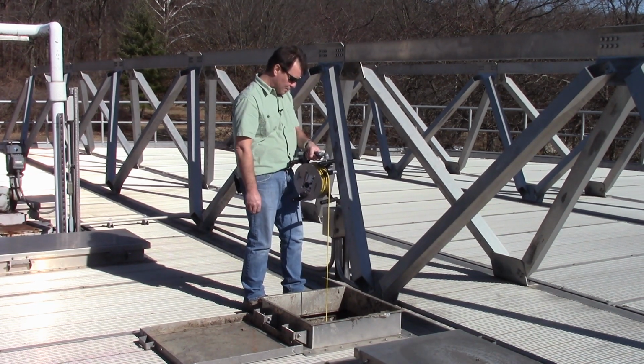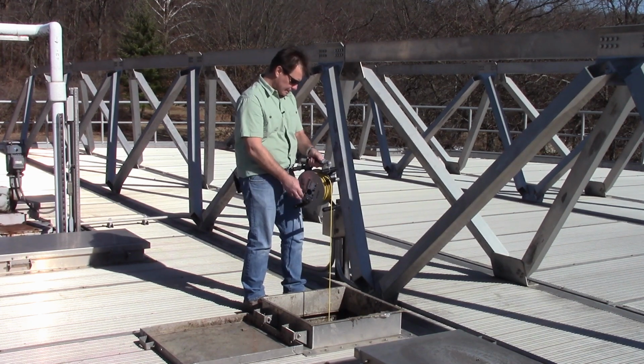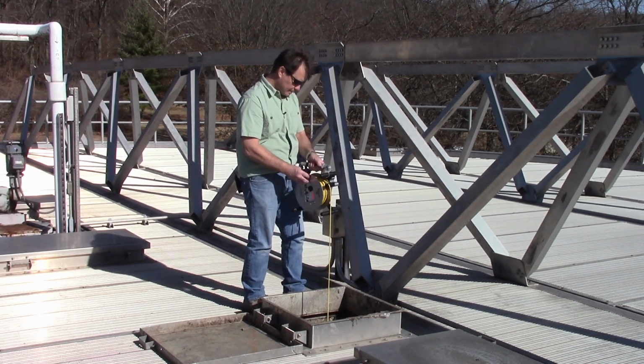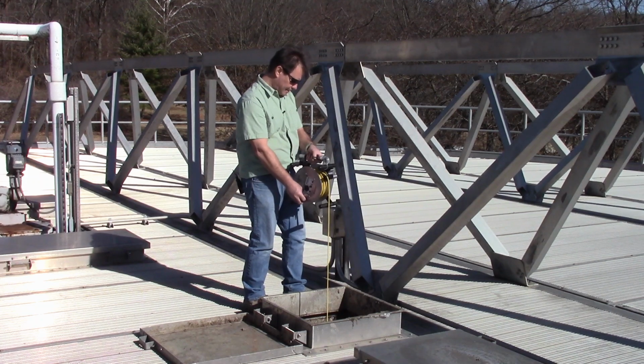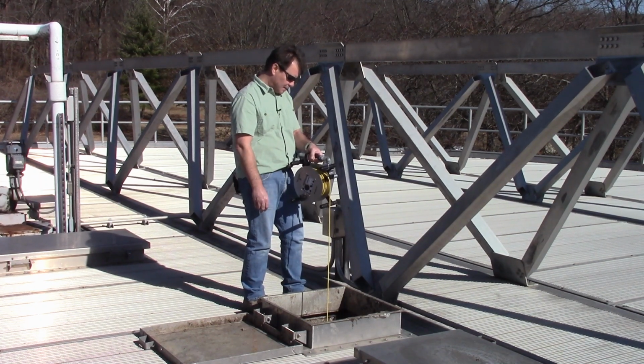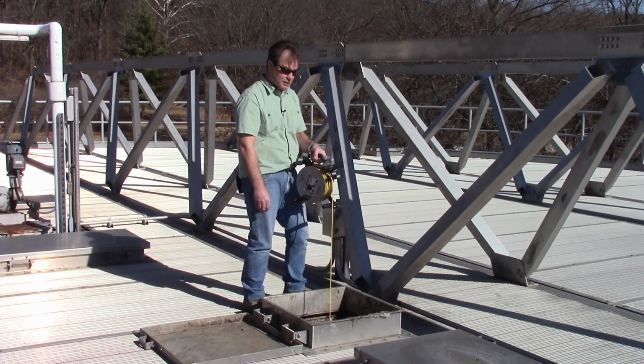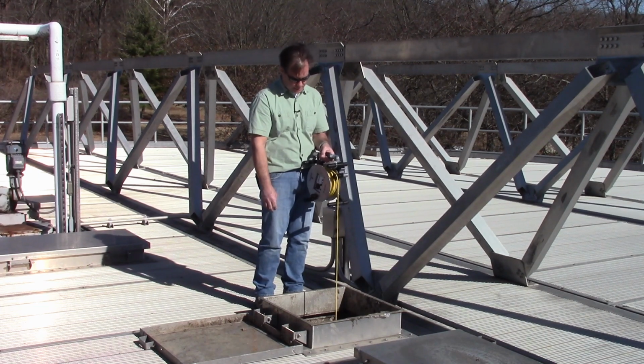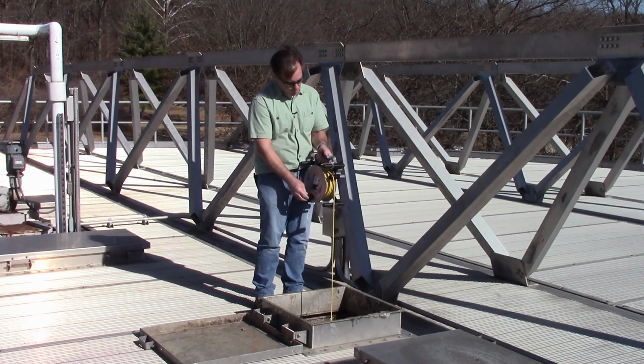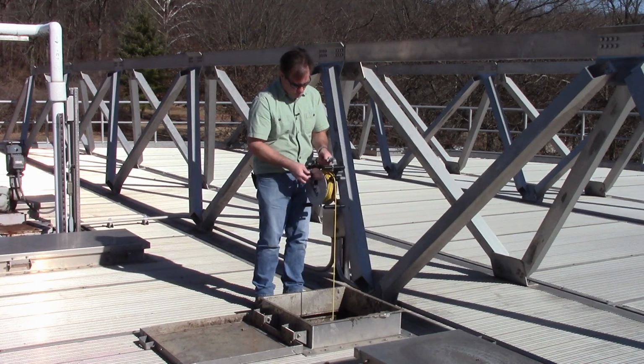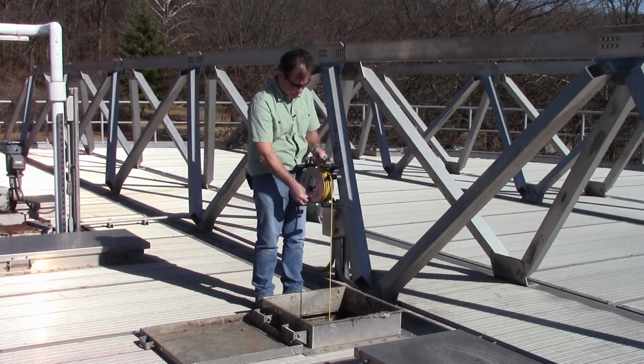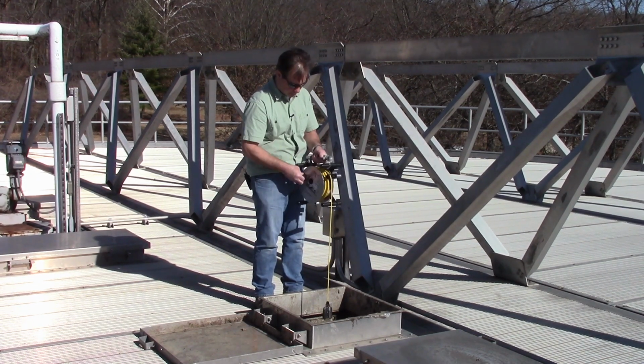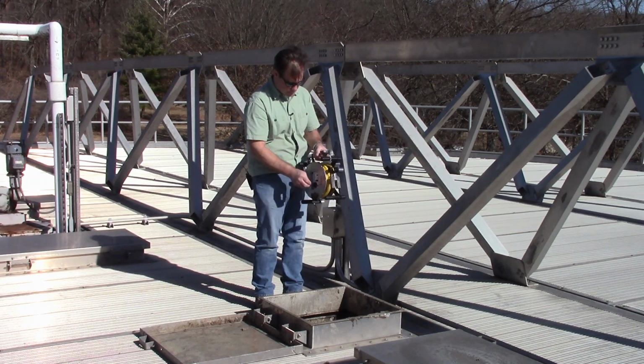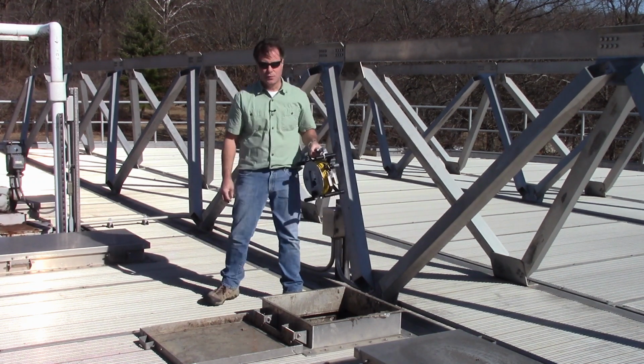Right there, the lights go out. I'm in. There, I'm out. That's 103 inches, which is much more than the 60 inches they expected. We'll note that amount, reel in the sensor probe, power down, and move on to the next tank.